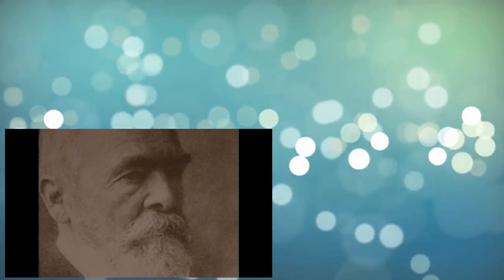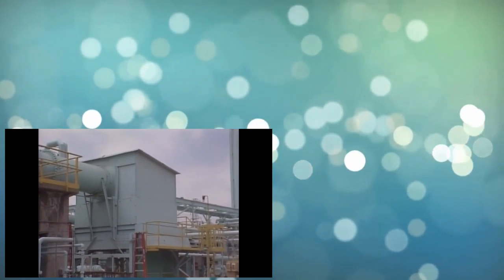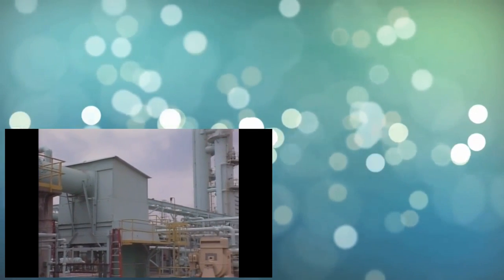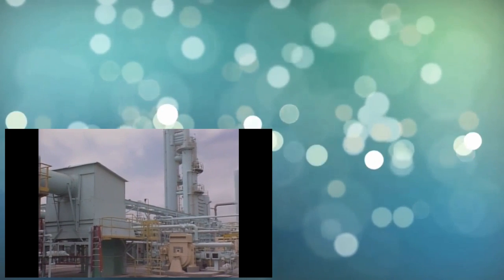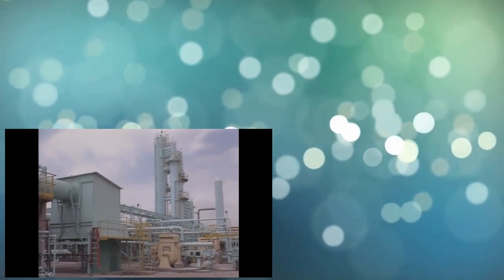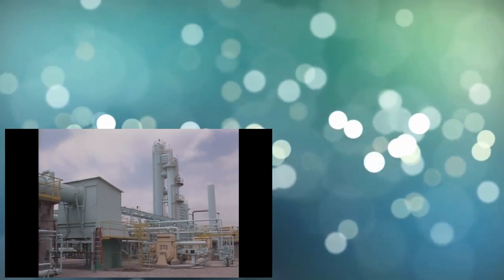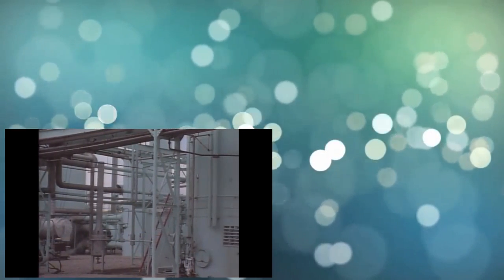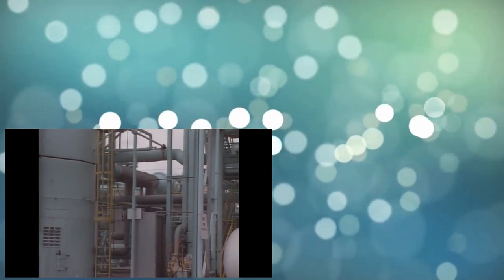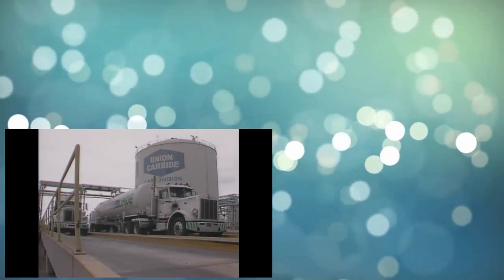In Dr. Linde's system, cooled, compressed air passes through the Joule-Thomson expansion valve. Gas that isn't liquefied is returned to the compressor by means of a heat exchanger, where the incoming compressed gas is cooled to a lower temperature by the outgoing cold gas. And the net result is liquid air.